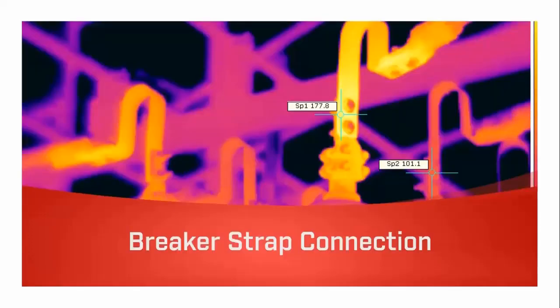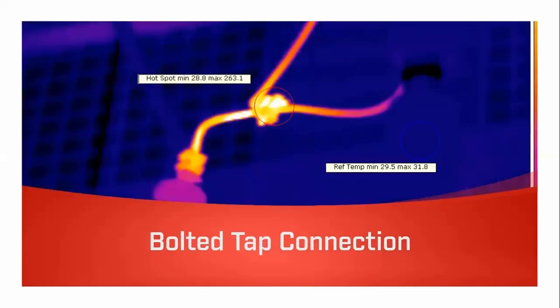Moving on to HV applications: this is a flexible strap connection — a transition from the round busbar to the breaker. The image is quite clear — the strap is warm compared to the other phases, indicating an issue, probably a loose connection on the bolted parts. The next image is a drop lead mechanical tap connection — out of focus, but the bare metal is oxidized from being outside long-term, giving it a fairly high emissivity.